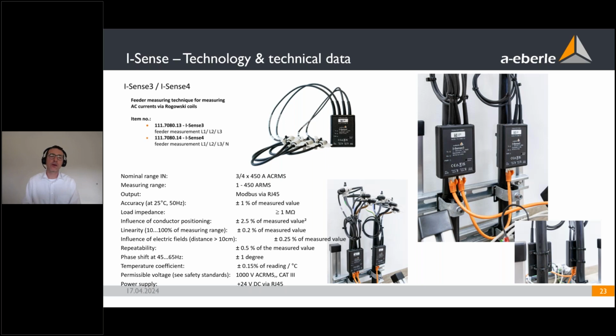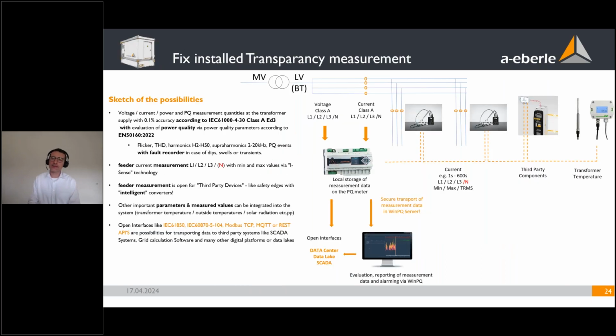This is needed because of what? Because of these things: we often have at the feeders third-party components which we can also add to our main PQ device, which is monitoring the transformer directly. We also have the opportunity to measure transformer temperatures and all these other things needed to see the reaction even from climate change, so the heating effects of a transformer, but also the effects of harmonics on the temperature of the transformer station.